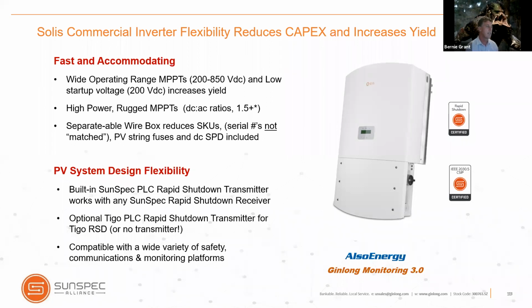Again, like I said, it has the rapid shutdown transmitter inside, or if you're going to use it on a ground mount system where you don't require a transmitter, you can order it without any transmitter as well, but you still get the separate wire box design. And that's for our 25 through 40 and our 50 through 66 kilowatt inverters. Very wide input voltage range. Again, they have the same flexible MPPTs that our single phase has.